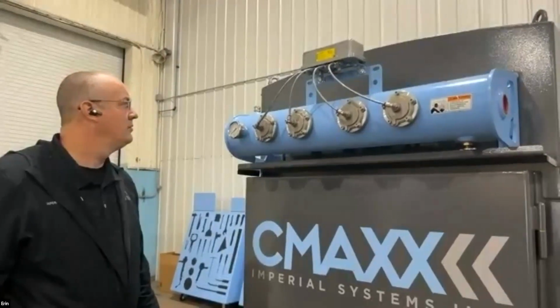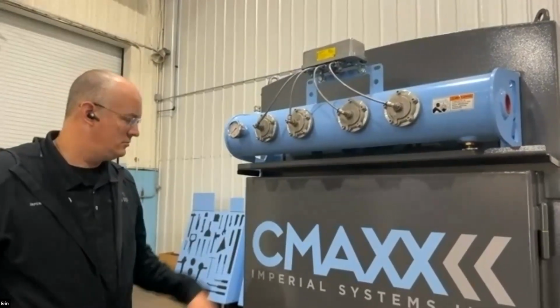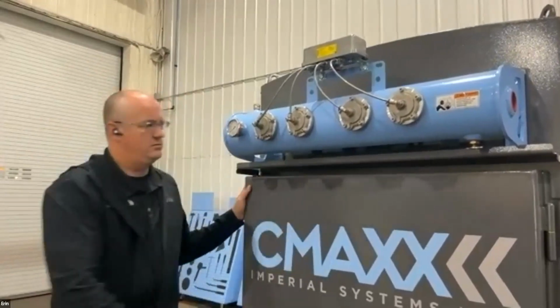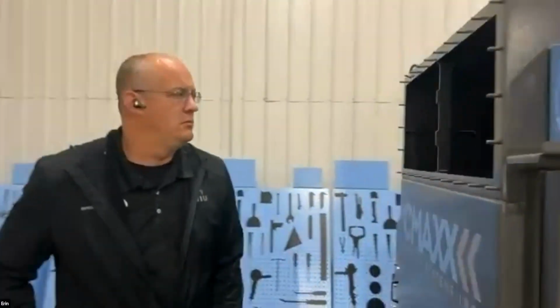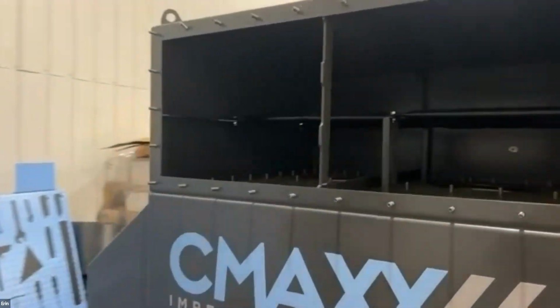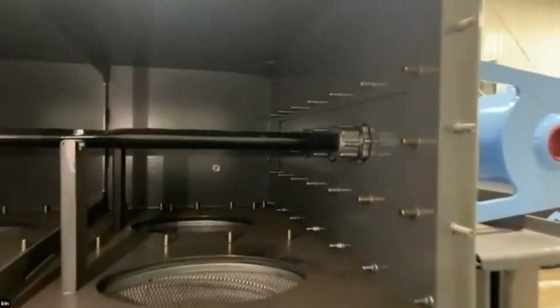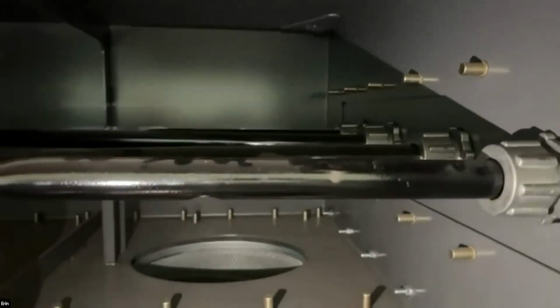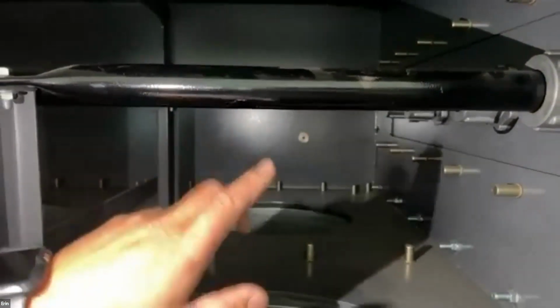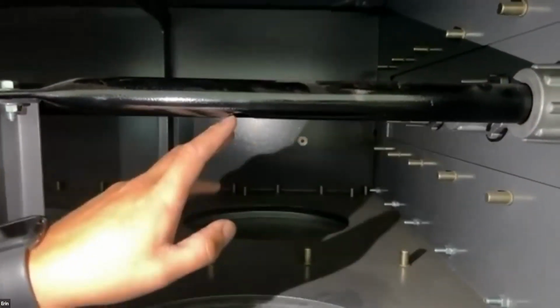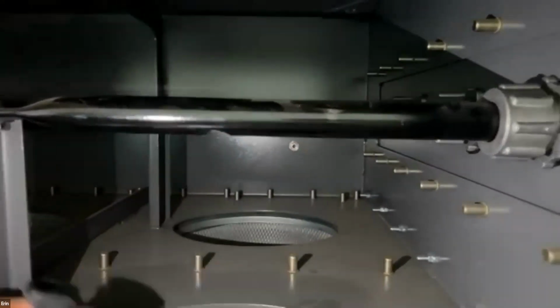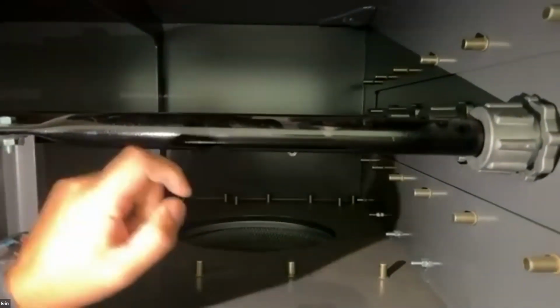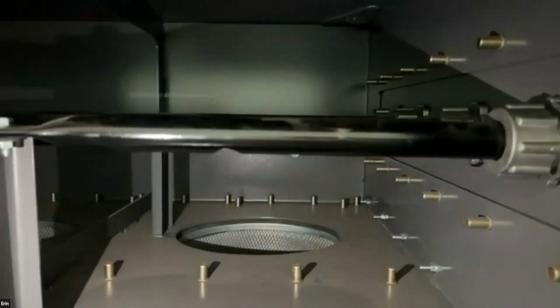Anyone want to see anything more on the collector on the inside? Real quick, Donovan, can you go back into the clean air discharge and show them those actual nozzles, and talk a little bit about how it cleans on the inside, where the air comes from? No problem. So when you're looking at this, there's just a hole in the pipe, and that is adequate to allow the air to pulse down into here. Some collectors will have a nozzle on here. This collector, because of the size and how it's set up, this is enough to clean this filter. That's all you need, just this hole to hit the filter hard enough to pulse it off.